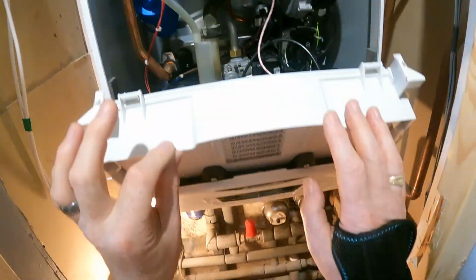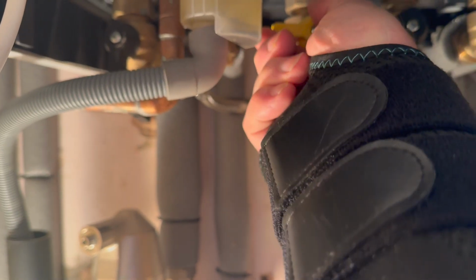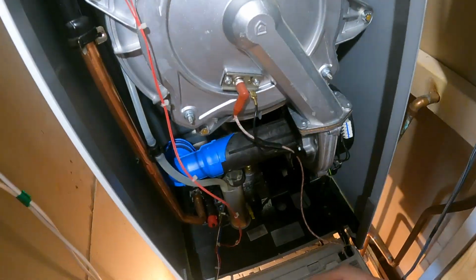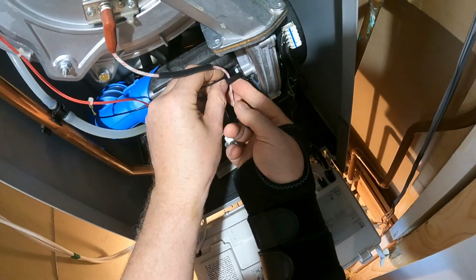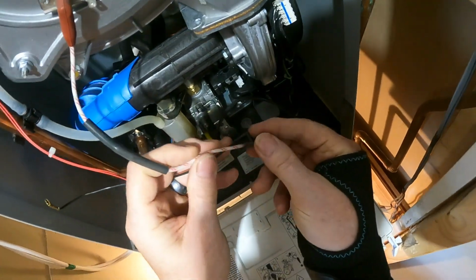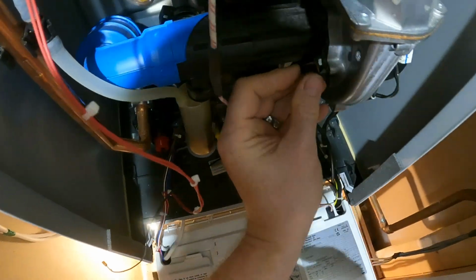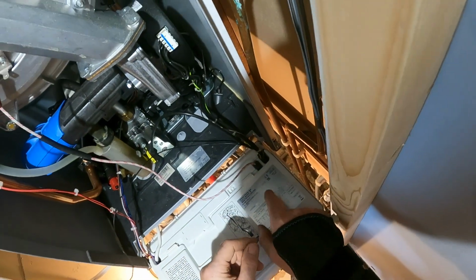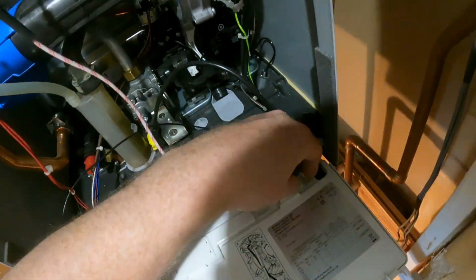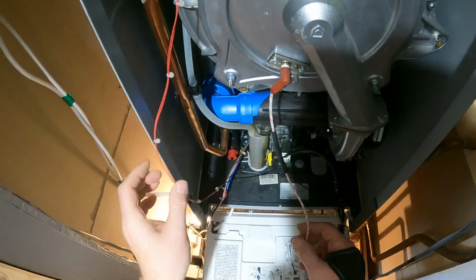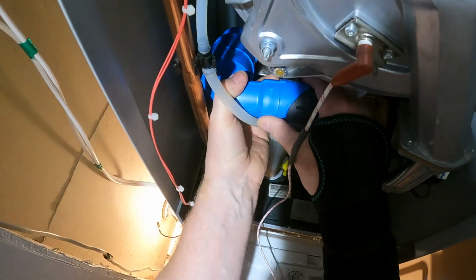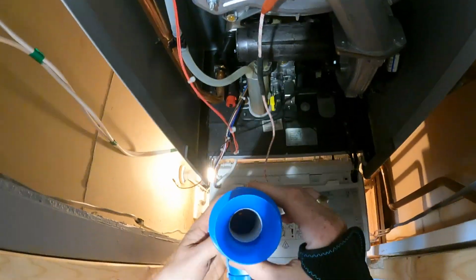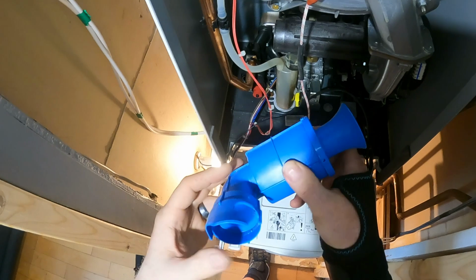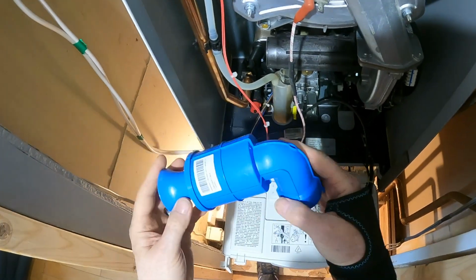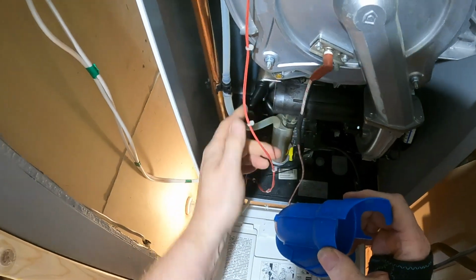Now to remove this, first thing I need to do is turn off the gas supply underneath. So that's off now. Now removing the electrodes, I need to pull the earth off, come out of this little clip here. I don't think that should have come off, but there you go. Should have come off that way. That goes back in there. Now this is connected to the board, so just clips off. Now this blue silencer, you have to twist it off, and inside here is a sponge which catches anything, and you can see that's clear. That's not where the noise is coming from, or doesn't look like the noise is coming from there, but we'll have a look inside there in a bit.